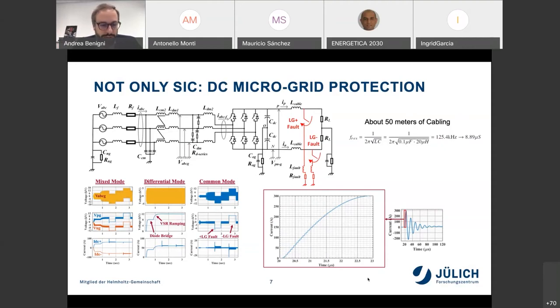We compare the results here. You can see the needed resolution from the resonance frequency of the network. With a resonance frequency of about 125 kilohertz, we have a period of about 9 microseconds, which would be hard to visualize with a time step in the range of microseconds.